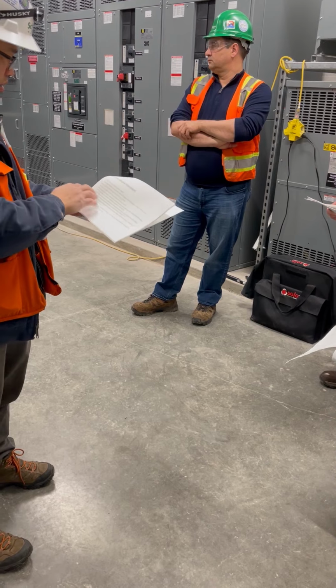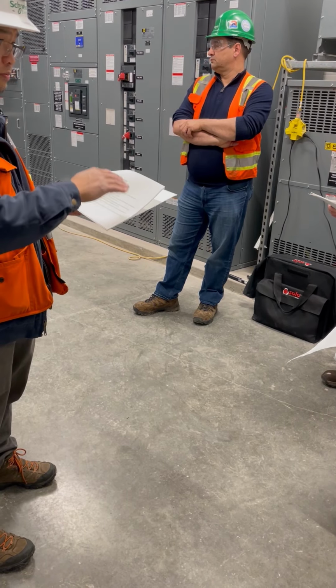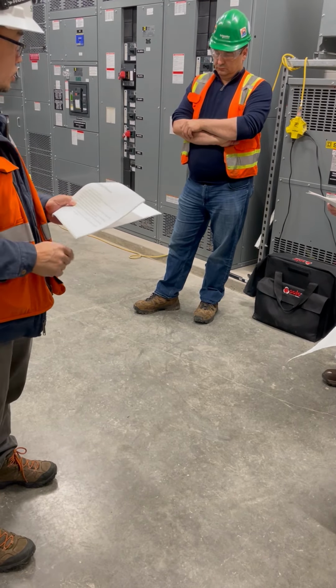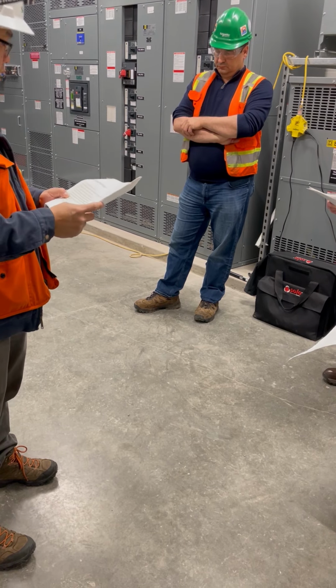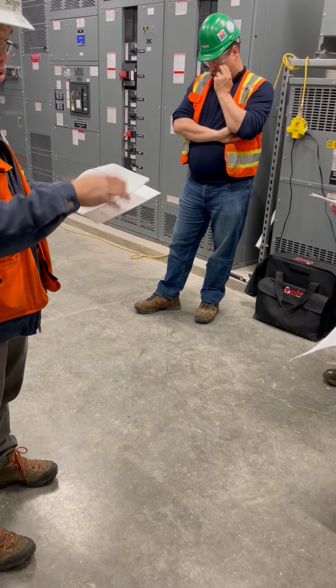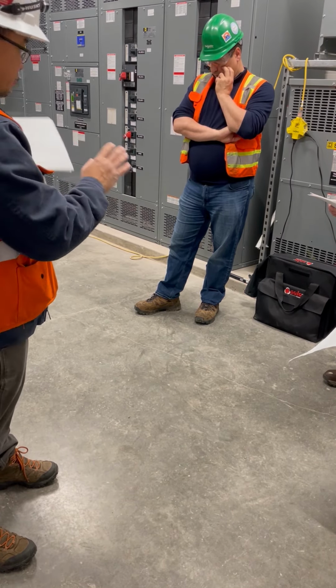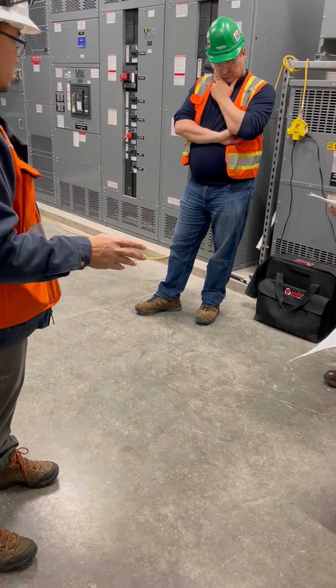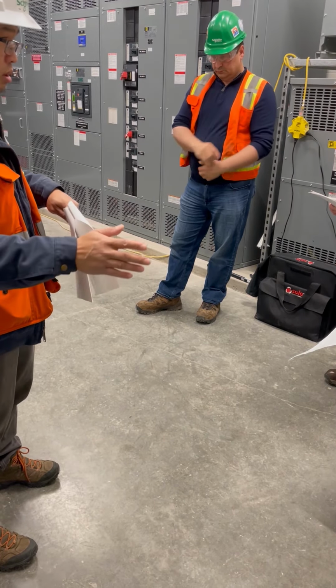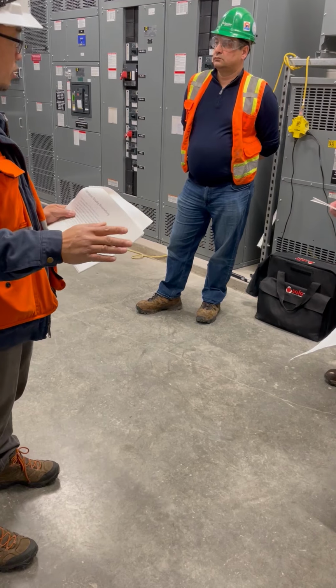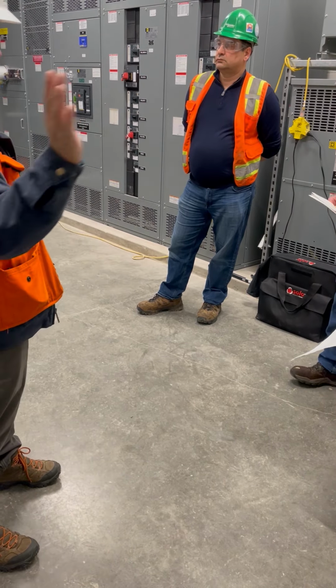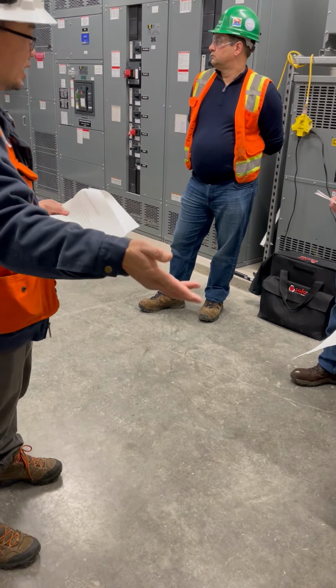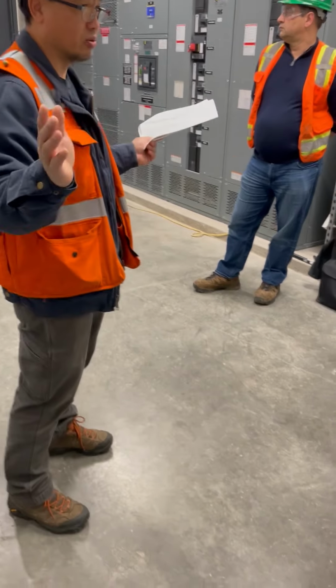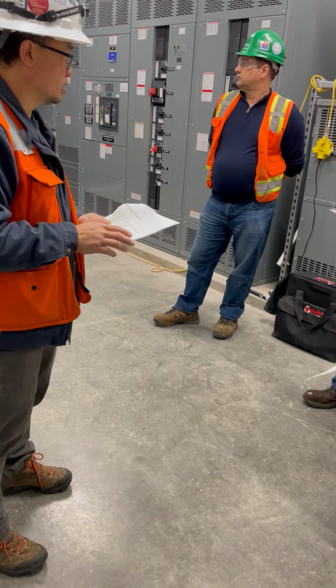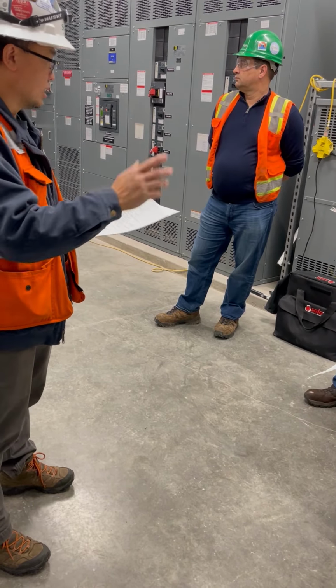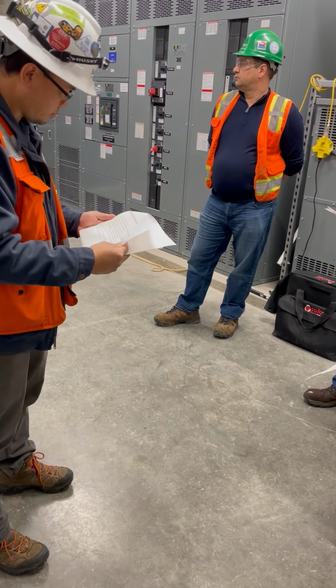So basically, the short circuit study determines the fault current level at each switchgear and panel board, and then from there we do the coordination. If there's a fault downstream, you don't want the main breaker to trip. You want a breaker as close as possible to isolate it. You don't want the whole facility shut down. You don't want a 20 amp breaker tripping the main breaker, taking out the whole school. So the short circuit coordination study does that, to the best extent, right?